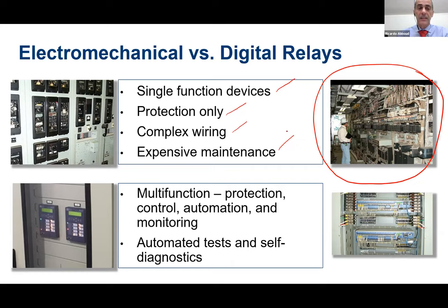So on the other hand, digital relays are multifunction. That means a single device can perform overcurrent, overvoltage, undervoltage, overfrequency, and different protection functions. And not only that, it's not only protection that they have. They also have control. So you can use the relay to replace control switches. You can use the relay to perform the control for the entire bay, and also for automation. So the relay will be a device that can supply data for different systems, for the SCADA, for the monitoring system. And it's a very good source to get data.